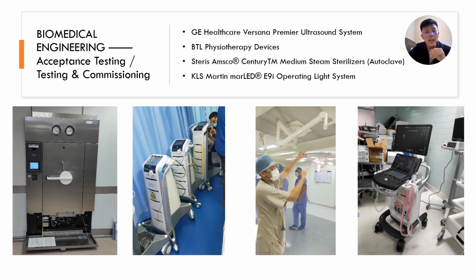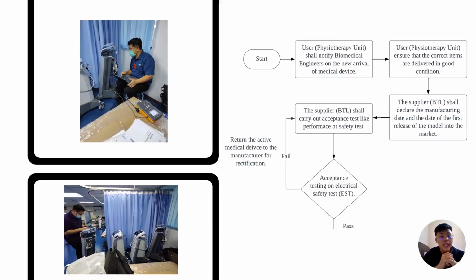In the coming slide, I will explain the procedure of testing and commissioning of new medical equipment using the BTL physiotherapy devices. To explain the process, I will be using a flow chart. First of all, the user, which is the physiotherapy unit, shall notify the biomedical engineers of the new arrival of the medical device. After that, the user shall ensure that the correct items are delivered in good condition.